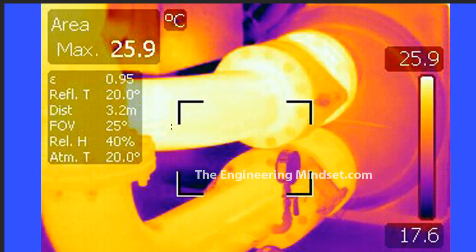There's one more thermal image showing the inlet and outlet of the condenser of the chiller. You can see that the water coming back from the cooling tower is flowing in through the bottom at 17.6 degrees Celsius, and it's exiting at 25.9 degrees Celsius to head up to the cooling tower. This is a slightly different temperature range than in the schematic because the schematic shows design figures whereas this shows actual figures. There will always be a difference between design and actual, depending on the load of the chiller, the outside ambient temperature and air conditions, and the load of the building — the amount of unwanted heat which you need to reject.